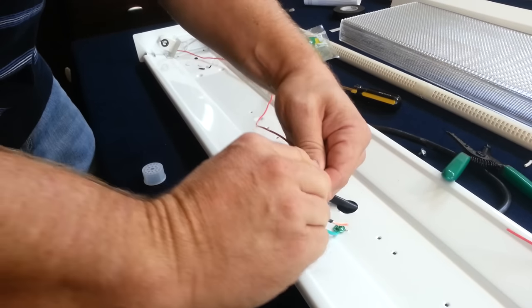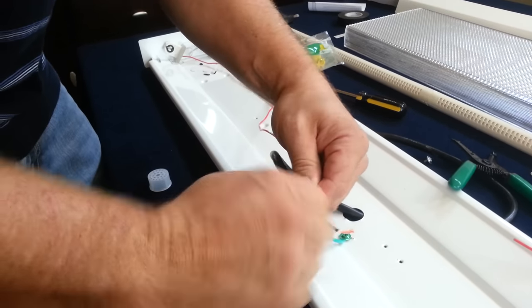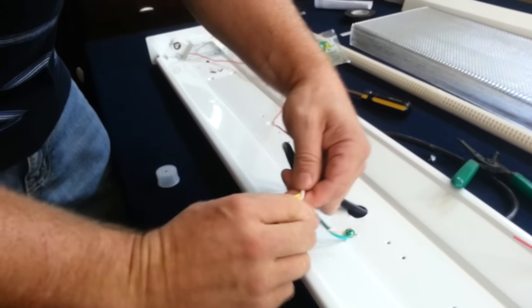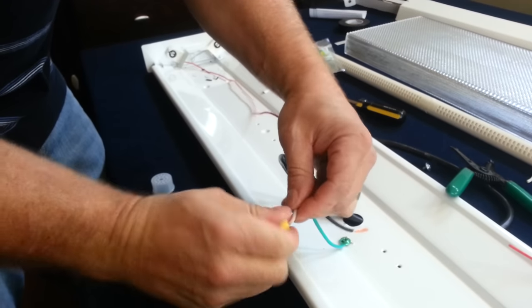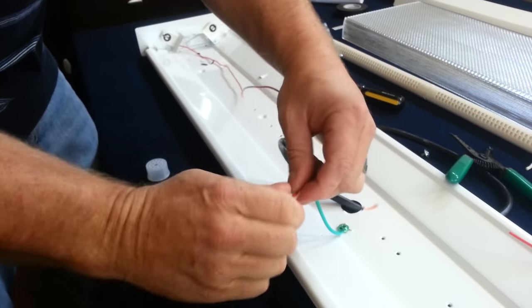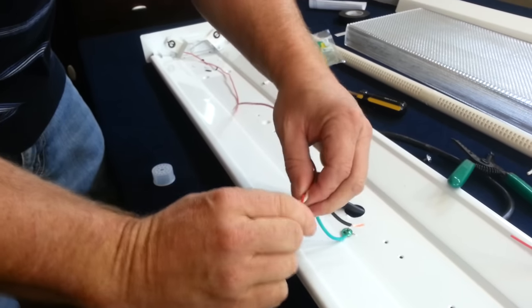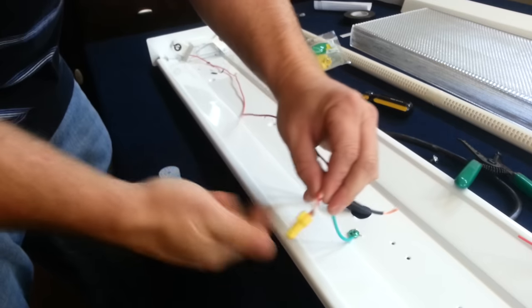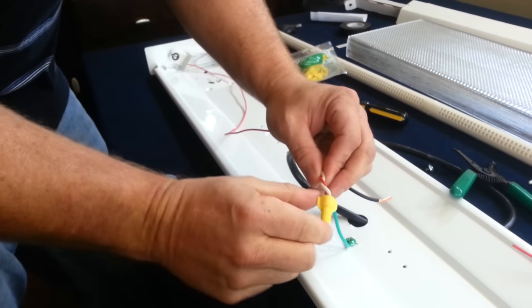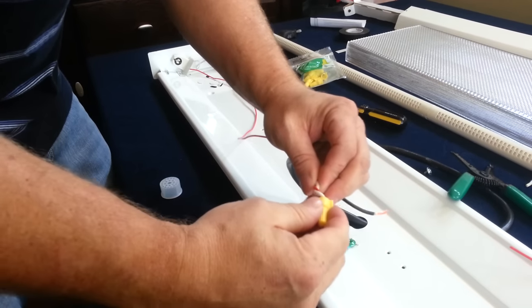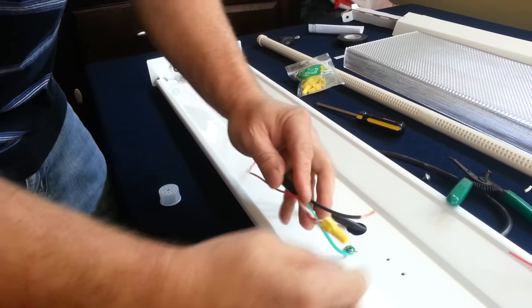Code in most states requires about one and a half inches of pigtail. As I twist this wire, you'll see it twisting around itself. Once we get about an inch and a half of pigtail, we know our wire is solid, give it a little tug, make sure it's in there, and we'll do the same to the other side.